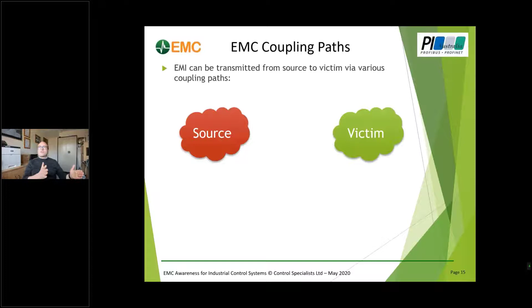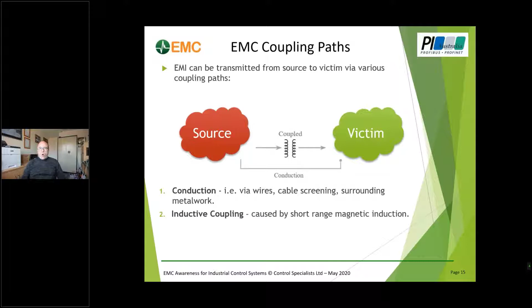If the equipment is close by - less than a meter or so, within the distances you'd get with cable trays, within a panel, etc. - we can have what's called near field coupling. There are two types: one caused by changing currents, called inductive coupling, and one caused by changing voltages, called capacitive coupling. Since we're using AC, by definition we have changing voltages and changing currents, so we will have some kind of coupling, and these are quite a big deal. This is one of the reasons why we'd want cable segregation, to keep this to a minimum.